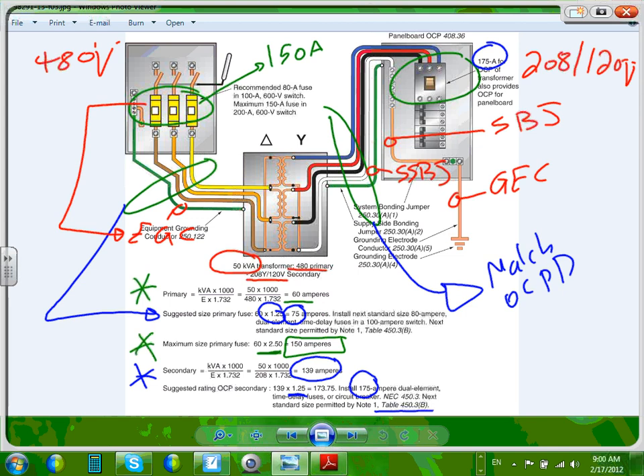For the time being, Jackson, my friend, I want you to understand that that green conductor coming from the panel to the transformer is called equipment grounding conductor. That conductor that's going to the ground is called a grounding electrode conductor. Tying the neutral to the ground is called system bonding jumper.